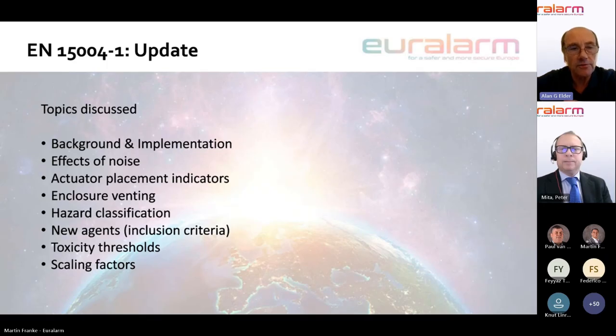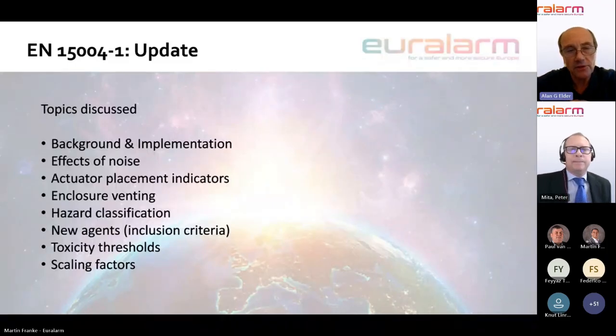We'll talk about the effects of noise, the new requirement for actuator placement indicators, references to an already published existing EN ISO standard on enclosure venting, a new section on hazard classification, new agents. How do we actually include new agents into the 15004 standard? A new section on toxicity thresholds, and finally finishing off with scaling factors which apply to Class B materials.